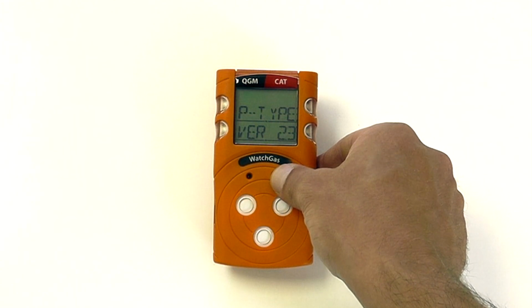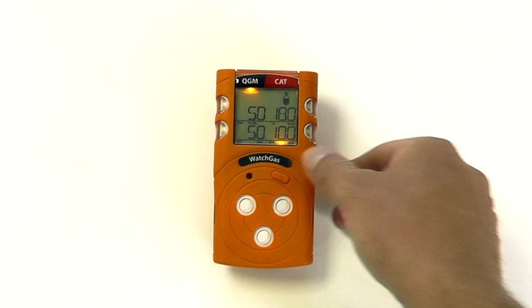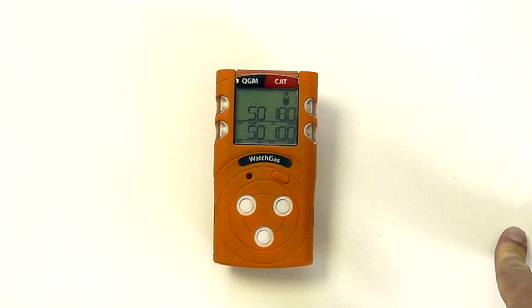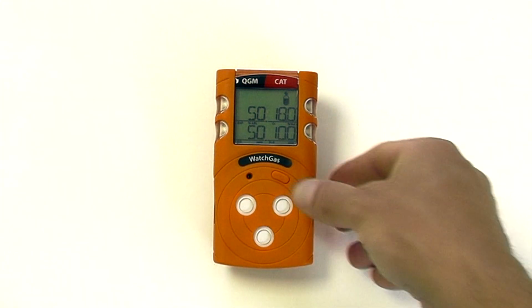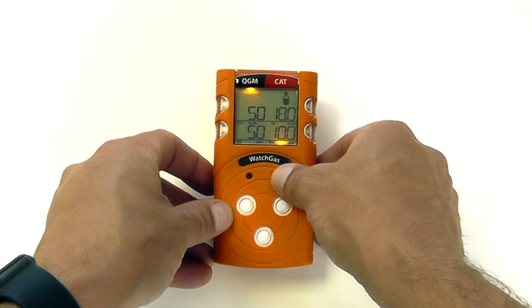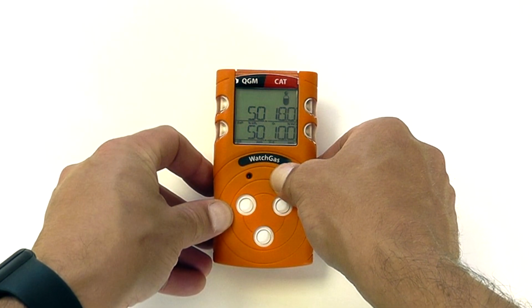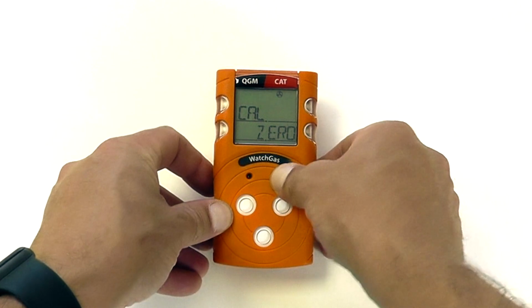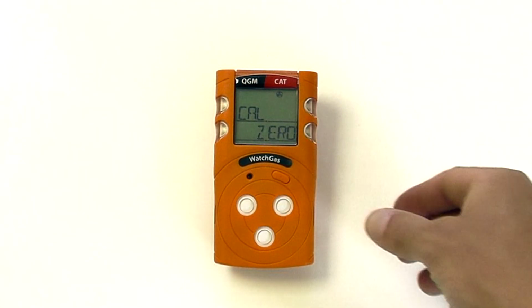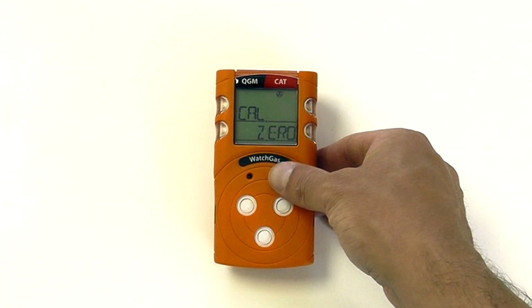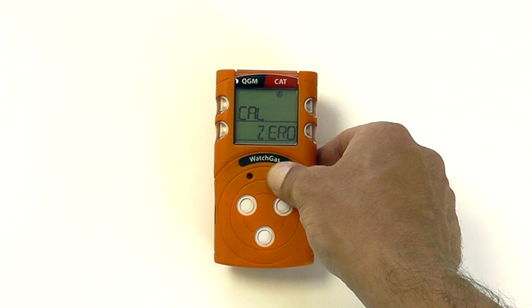We can look at the type and version. And then these are the calibration factors and thresholds for this particular device. Now to enter calibration mode, when you get to this section, press and hold, and you will now enter the user calibration function. Firstly it'll ask you to do calibrate 0, so press and hold.